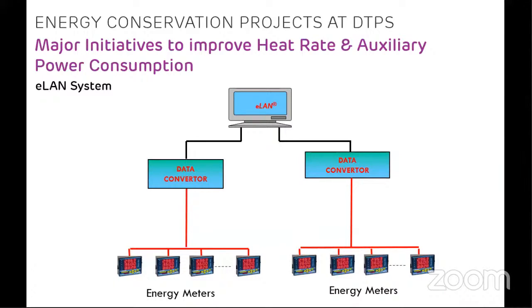So the ELAN system consists of a centralized database which gets data from data converters, which in turn get data from energy meters. Each motor, or even each individual feeder, in the plant has an energy meter installed on it. These energy meters measure the data, which is the energy consumption of the equipment. They feed it to the data converters, and the entire data is fed to an ELAN monitor, a centralized monitor, which generates reports and signals, and this data is accessible to the key members of the plant.